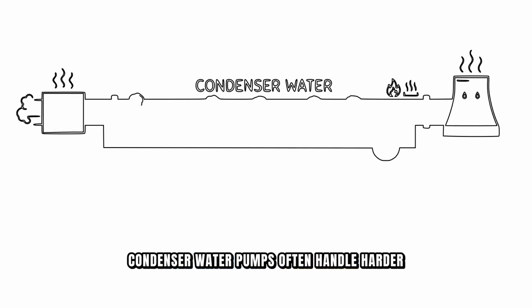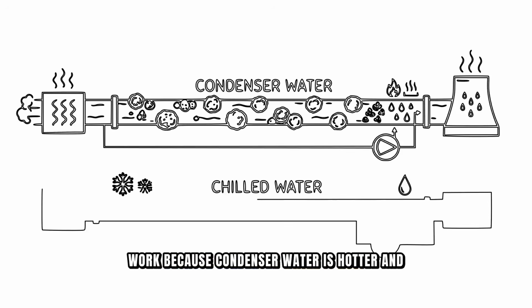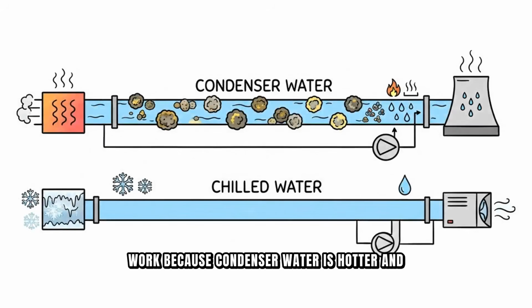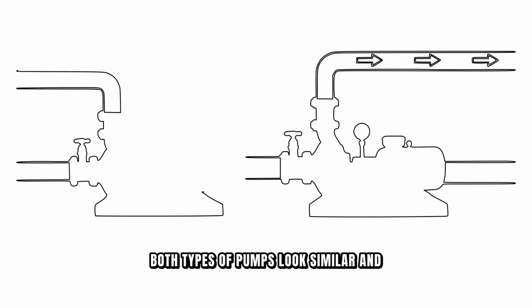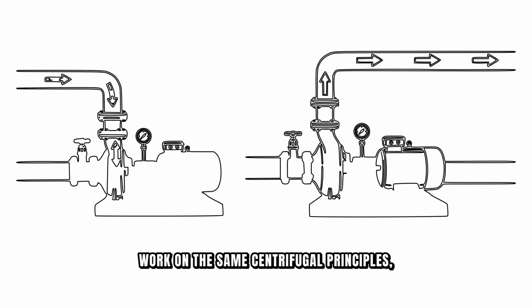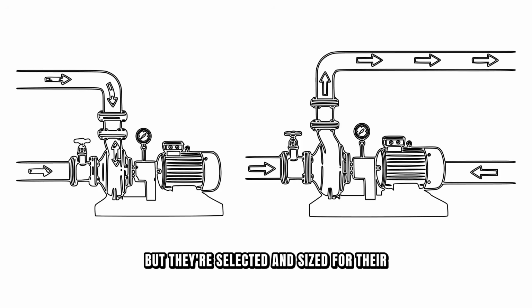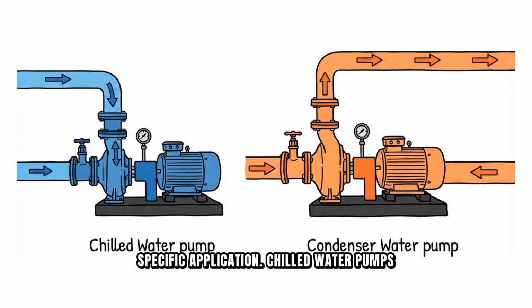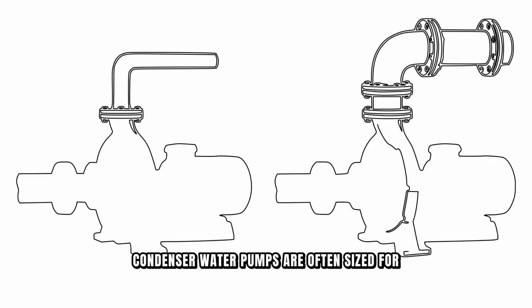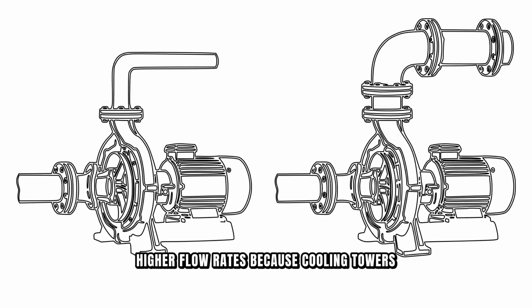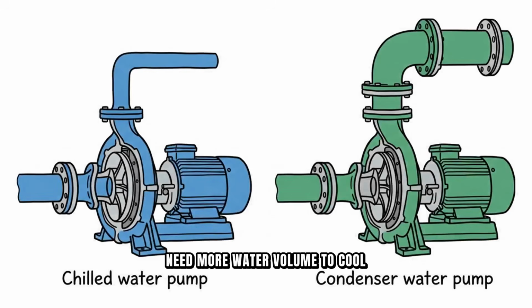Condenser water pumps often handle harder work because condenser water is hotter and more prone to scaling and corrosion. Both types of pumps look similar and work on the same centrifugal principles, but they're selected and sized for their specific application. Chilled water pumps are usually sized for moderate flow rates and lower pressure requirements. Condenser water pumps are often sized for higher flow rates because cooling towers need more water volume to cool effectively.